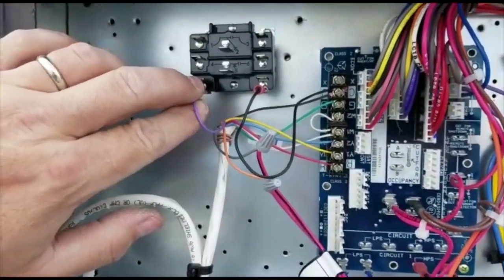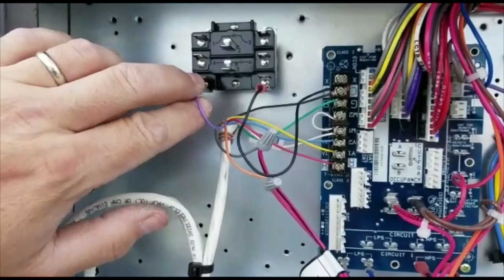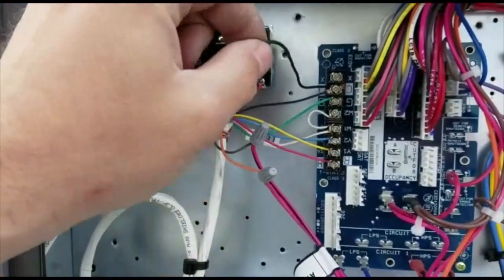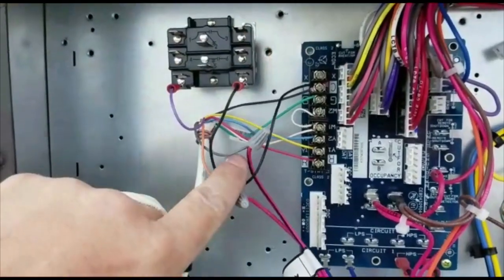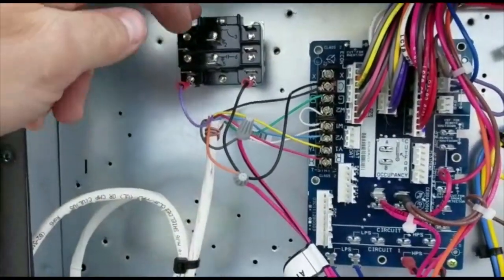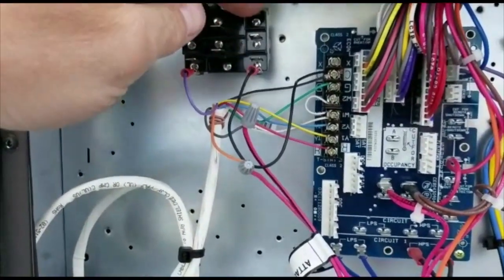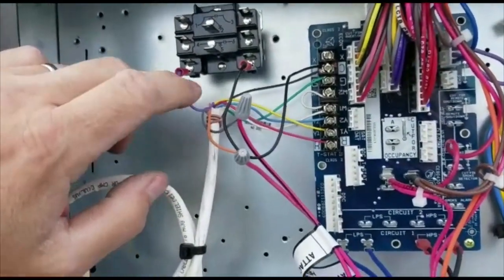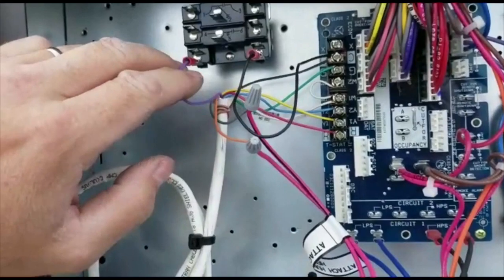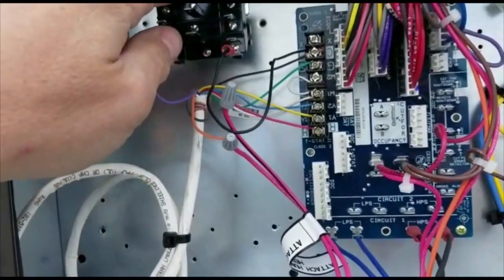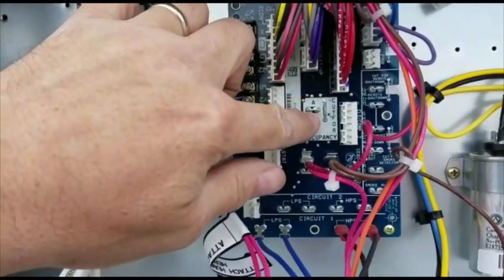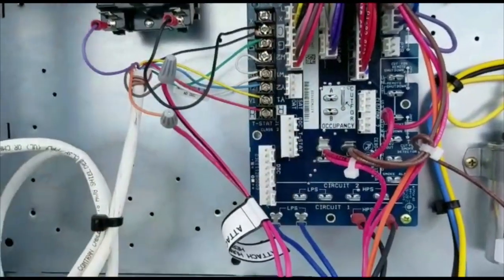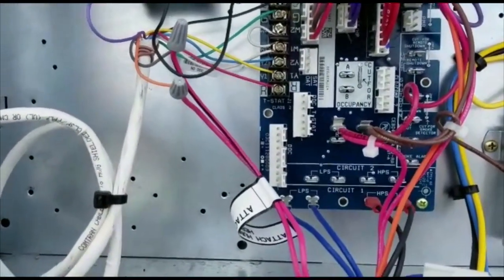...on our Wi-Fi thermostat. We have a common going to common on the board, and then we're coming out of the normally open set of contacts. So when the thermostat's programmed, the 24 volts will be sent to the relay, closing the contacts and allowing the board to run the economizer and ventilation better.